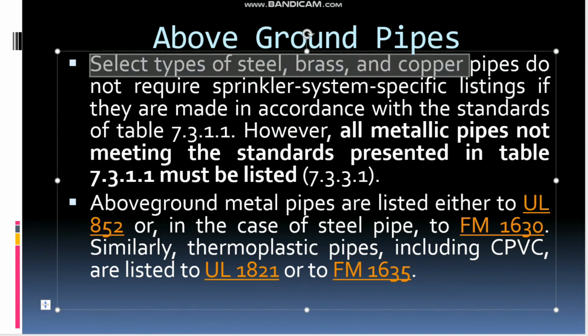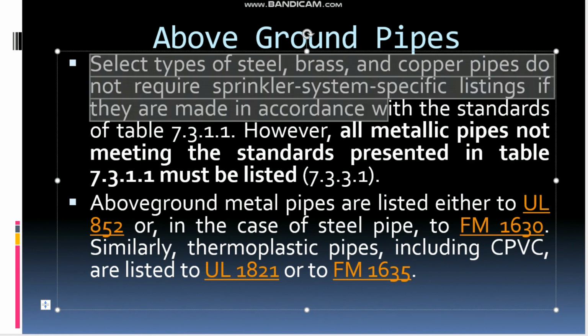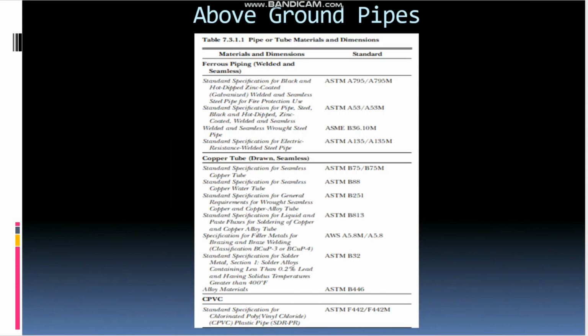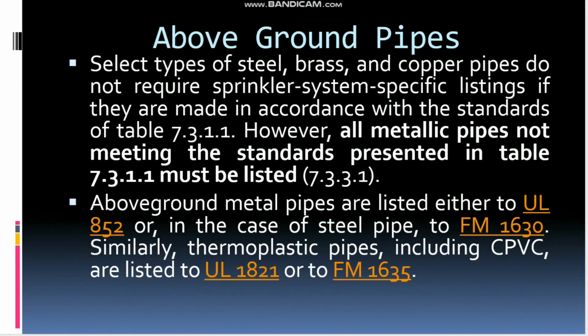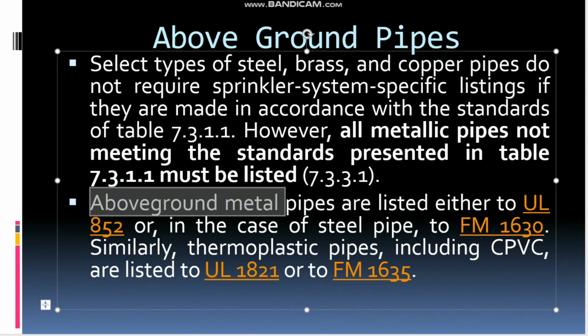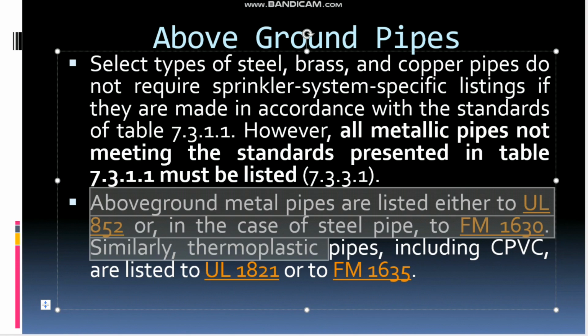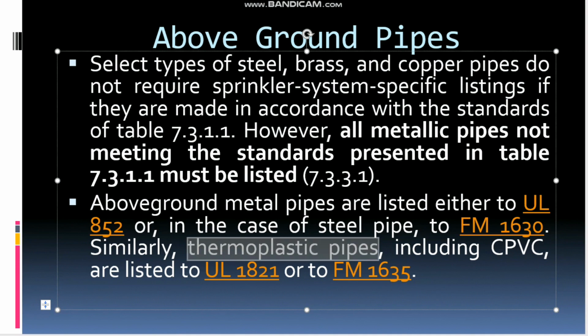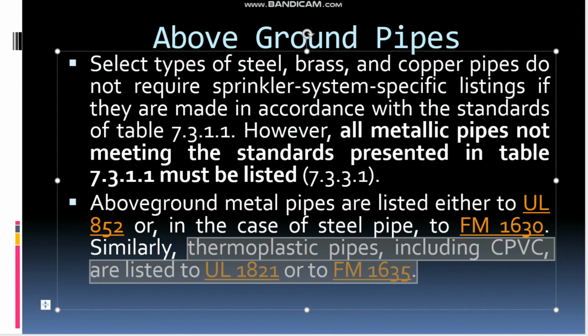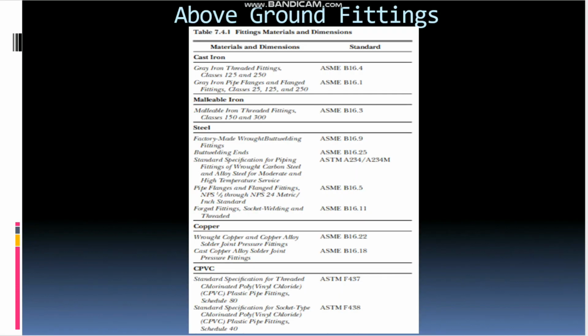Select types of steel, brass, and copper pipes don't require sprinkler-system-specific listing if they are made in accordance with the standards mentioned in this table. So if you are following this table, there is no special requirement to have listed pipe. But if you are taking the material from outside of this table, then surely it has to be listed. Coming to the listing, above ground metal pipes are listed either to UL 852 or, in the case of steel pipe, to FM 1630. Similarly, for thermoplastic pipes, including CPVC, we can go with UL 1821 or FM 1635. And similarly to pipes, we have a list of fittings also; we can choose the fittings from this table.